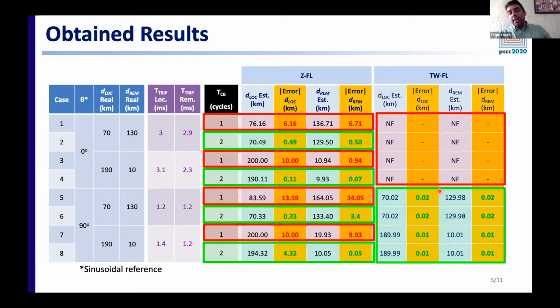Regarding the traveling wave-based fault location method, as you can see here, when we have transients induced by the fault, like faults initiated close to the voltage peak, the results are amazing. Very accurate functions were used here, with errors of about 20 meters only. But in cases when the transients are overdamped, these algorithms are not expected to operate. So we need further development in that.